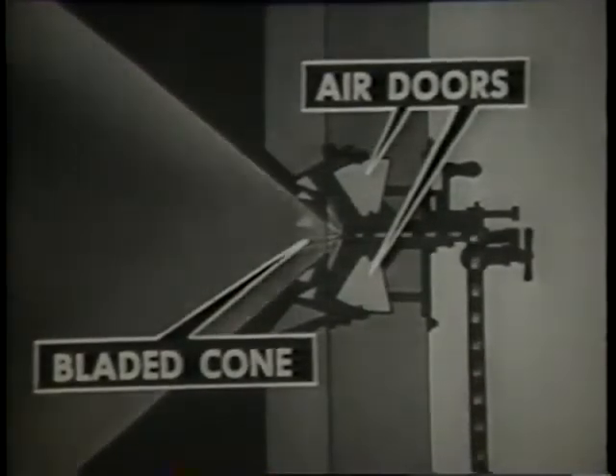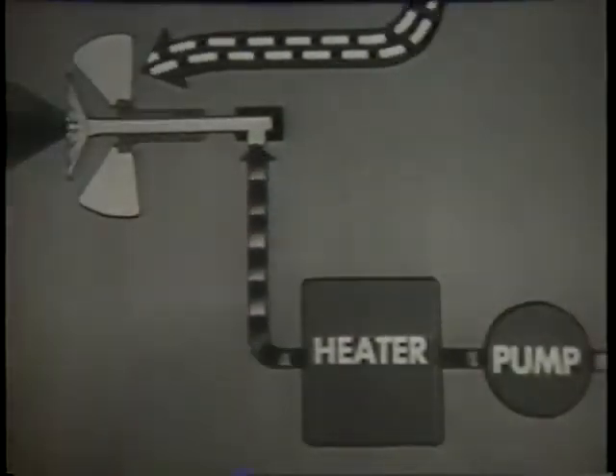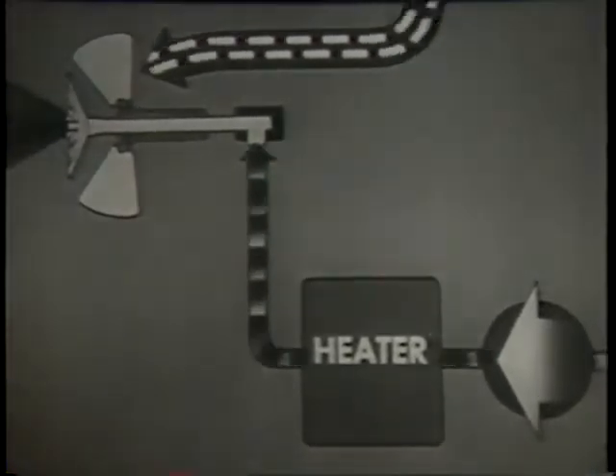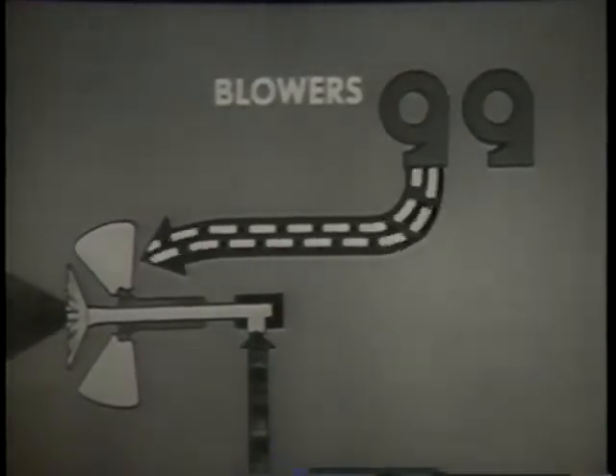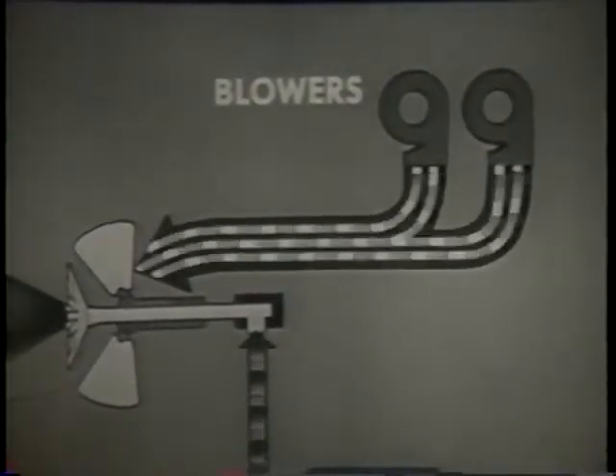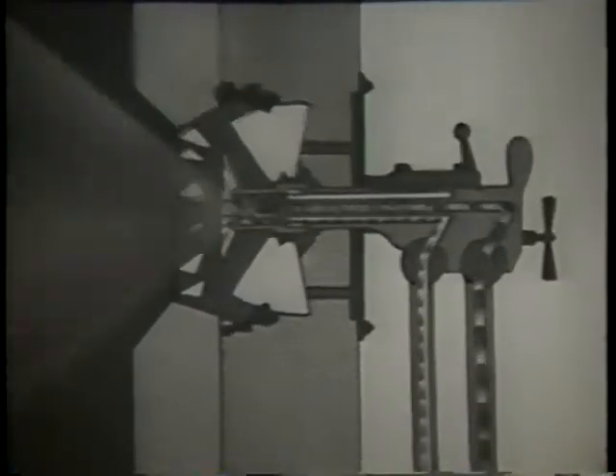In burners with mechanical atomizers of the pressure type, the sprayer plate atomizes the oil, heated and under pressure. The register gives the blast of air from the blower a rotating motion and mixes the air with the oil. You vary the pressure on the oil supply line to control the amount of oil entering the furnace. You vary the speed and number of forced draft blowers. In the return flow burner, you vary the pressure on the return oil line to control the amount of oil entering the furnace.